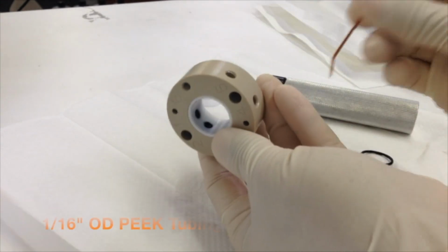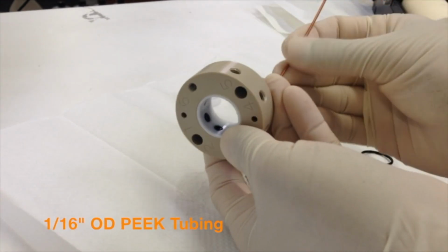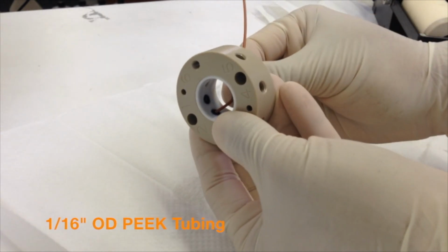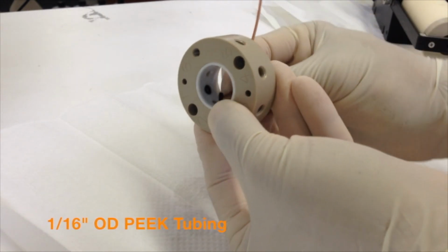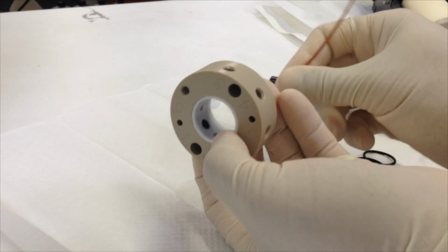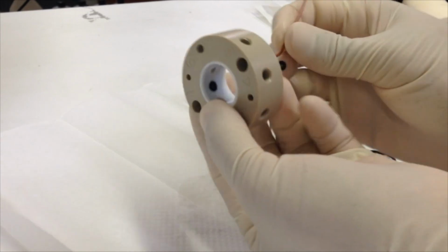Use a piece of 1/16" OD PEEK tubing to remove the 5 small O-rings. Do not use any sharp tools, as this will scratch the soft white plastic of the valve.